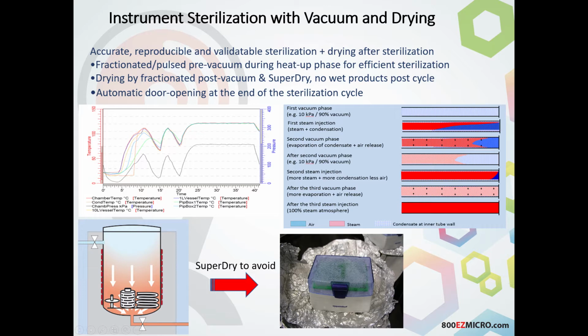So at the top left, you'll see a diagram here. If you look at the items on the chart on this graph, there are different vessels that we've placed inside of the unit, and different items are going to achieve temperature at different times. Those pulses that you see are vacuum pulses with steam inlets into the unit. So you'll see when we first begin that we have quite an array of where all the temperatures are across the board for all of these different items. Once we've achieved that 3rd vacuum pulse and then the next steam pulse when we go to sterilization, you will see all of those lines are completely congruent at that point. So we're not going to have any differential. Even if we have a 10-liter vessel, a 1-liter vessel, pipette tips, by the time that we've pulled all of these vacuum cycles, we're going to be able to achieve complete sterilization.